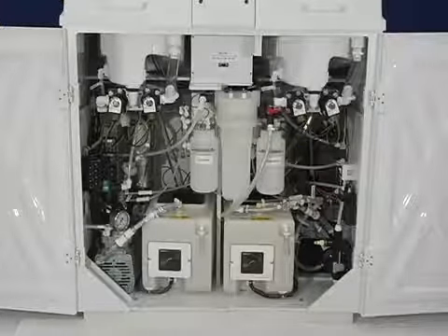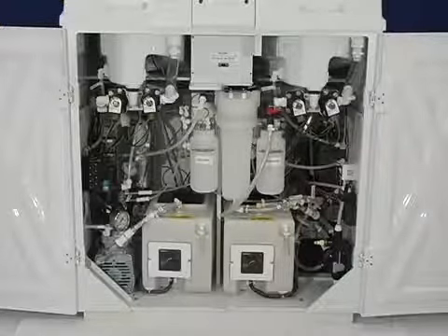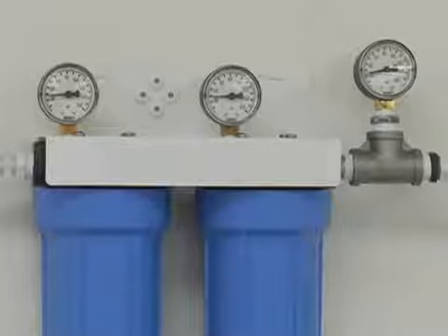The individual filters must be replaced as necessary. More frequent replacements may be necessary depending on the water quality in your area. Low water flow or a drop in water pressure during flush or rinse cycle of 10 or more psi between gauges are indications of a need to change filters. Typically, the unit will have an increasingly longer rinse time, followed by low chamber alarms in the rinse cycle as the filters become blocked. Inspect each gauge to determine which filter to replace. The largest pressure drop is indicative of the filter that needs to be replaced.